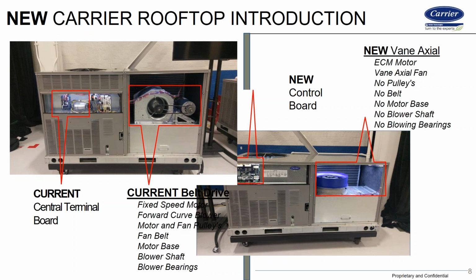And since this really is an SAV, or we'll call it constant speed, high-low type unit, you're going to have some type of either barometric bypass or an actuator controlled bypass damper. So again, this isn't a VAV setup here. Although it's 2-speed SAV, they're constant speed. Right, and that situation would be the same whether we had one with a VFD on it, whether we had one that was belt driven. All those things would be the same. You'd open all the dampers to wide open, set everything up for the highest CFM, and set your bypass based on that. And then when things ramp down in real life, they just happen to ramp down. Correct.